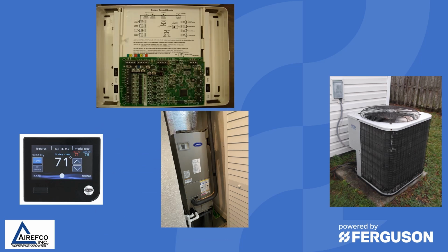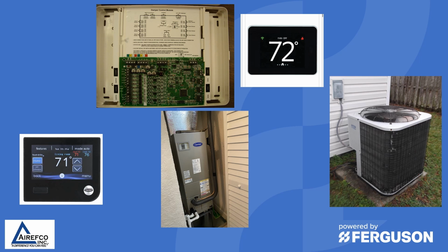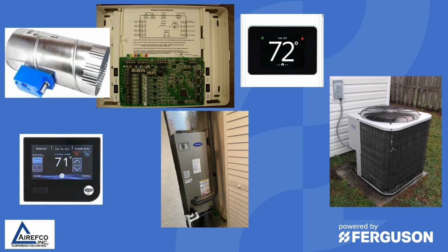In this case, we had a zone system with a zone board and a smart sensor in a second zone, and then of course your damper controls. The system was not communicating. When they would try to have the user interface find all the components, sometimes it would find the indoor unit and sometimes it would find some other components, but the communication was very sparse. And so we had to figure out what was causing the lack of communication on this system.